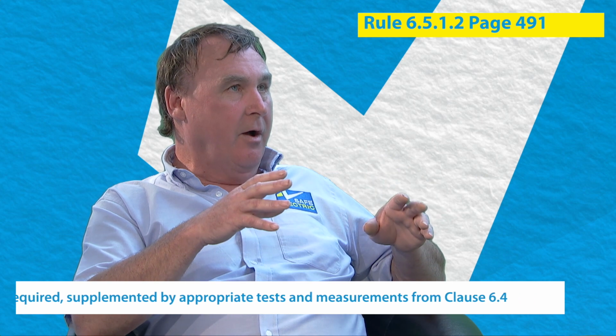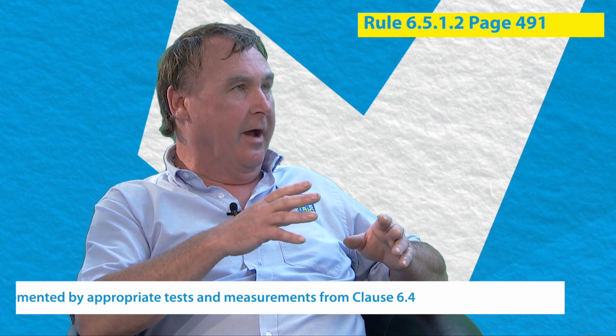The important thing to note here is that I hear lots of electricians say to me when I'm doing my job, oh, I was afraid to do that test. I was afraid I'd damage equipment. If you do the test incorrectly, you will damage equipment. But if you do the test correctly, you can't damage equipment. So you have to be confident as an electrical tester that you can do the test correctly and you won't damage equipment.